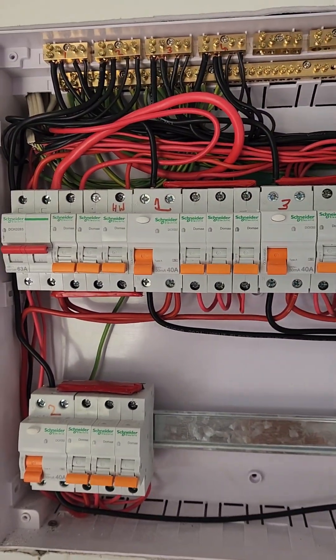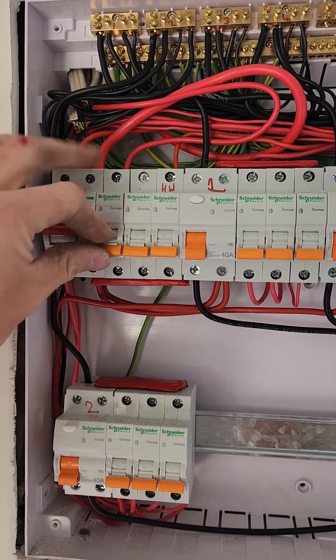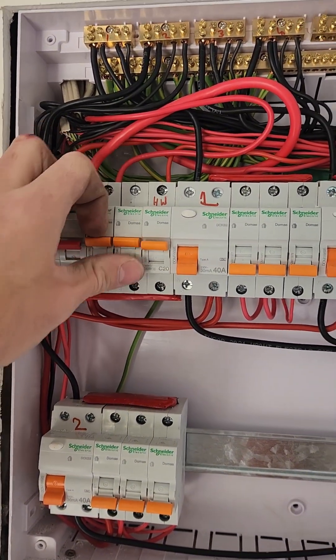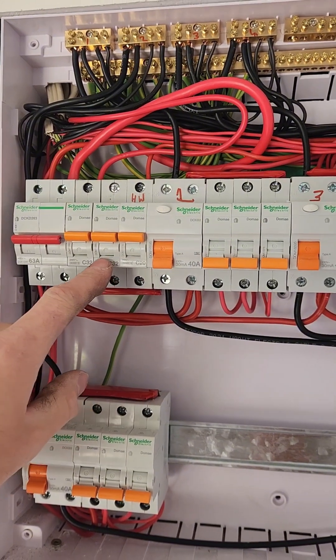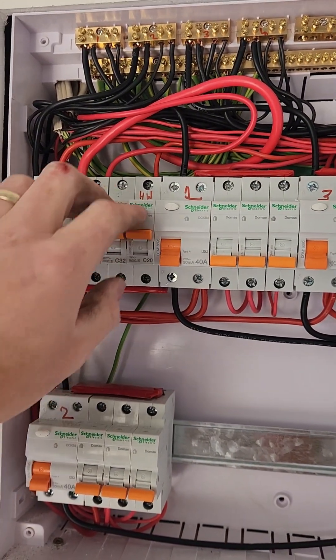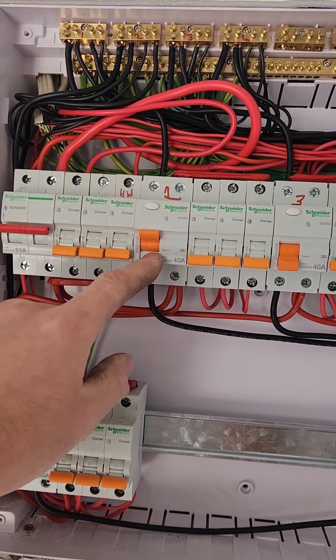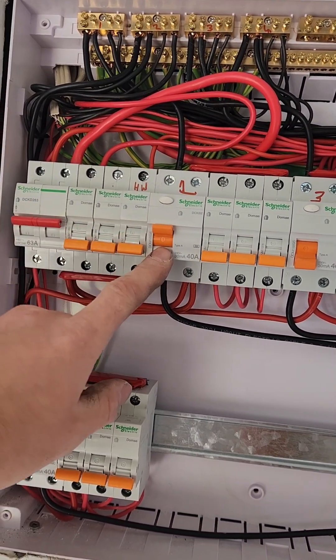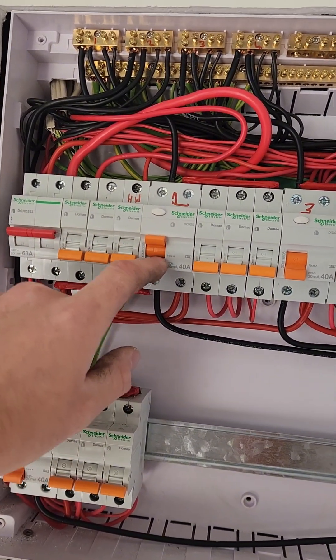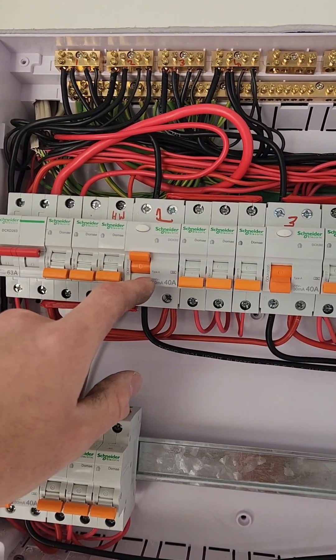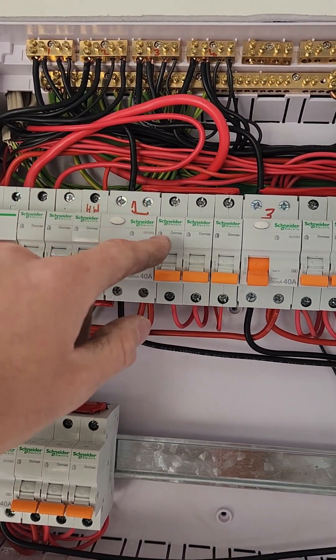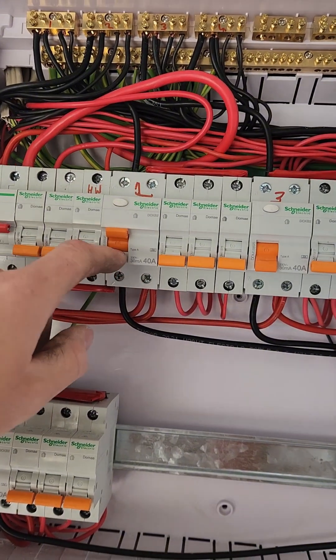Now for those of you who don't know, this is an MCB or a miniature circuit breaker and those are designed to protect the circuit from over current. This is an RCD. An RCD is designed to protect people, so it detects if there is a leakage to earth via an imbalance in the current leaving from the RCD and the current coming back through the RCD.